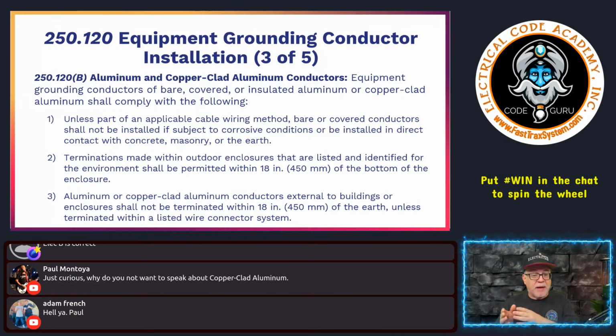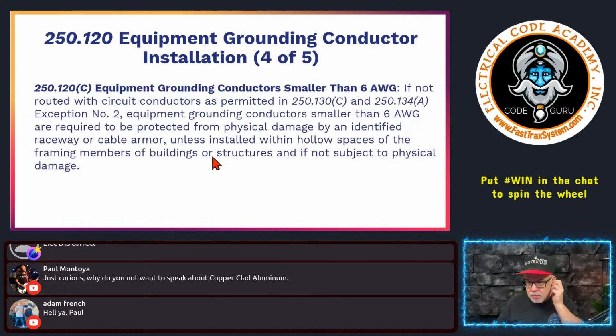And that termination on a bus, unless it's in an enclosure that's rated for the environment outside where you're going to be terminating, or if it's external and it just happens to be running outside. I don't know when you would have an aluminum or that other type of conductor running external to a building, unless it's in a raceway, and then it comes to some kind of junction box where it terminates. Well, then you have to make sure that's not within 18 inches unless that enclosure it's terminating in is rated and sealed and is part of a listed wire connector system, whatever that is. You can Google that type of thing. So, you with me? All right.